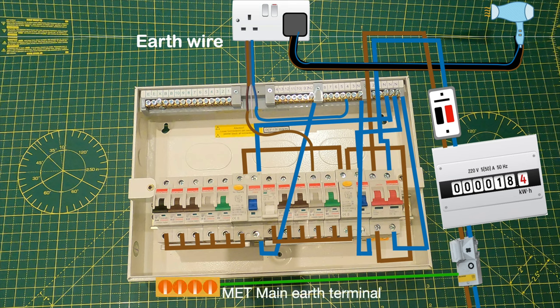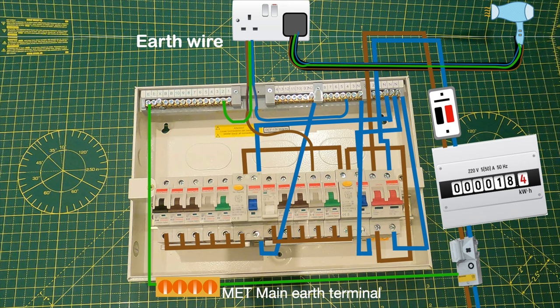From the main earth terminal it makes its way to the earth terminal of the consumer unit. The twin-and-earth cable coming from the socket circuit includes an earth wire to attach to the earth terminal bar in the consumer unit, and the earth wire then makes its way over to the appliance you have plugged in. It's important to note that not all appliances have an earth wire — this might be because it has a plastic casing or the live wire has been designed so it can't touch the casing should it come loose. In the event of a fault, if the earth wire isn't installed correctly and the live wire were to come in contact with a metal casing and you touched that casing, you would get electrocuted.